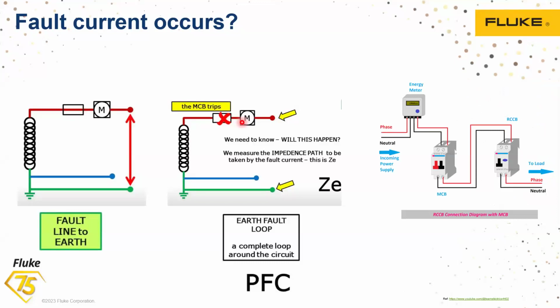It also determines how easily the fault current can flow through the circuit. Now, a lower impedance path also helps the circuit lower the total impedance and carry the fault current more easily, right? So to ensure safety protection, the earth fault loop impedance should be kept within the acceptable limits specified by the electrical safety regulations. If the loop impedance is very high, what can happen?